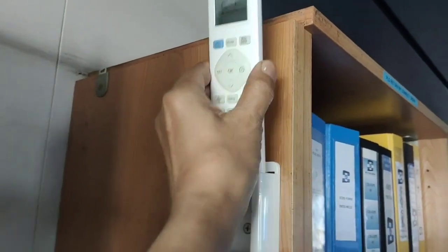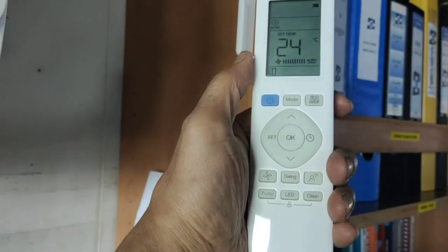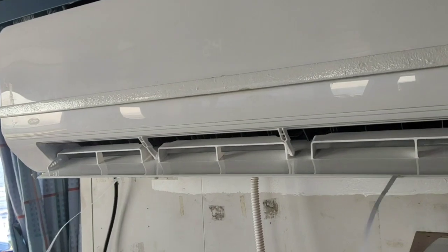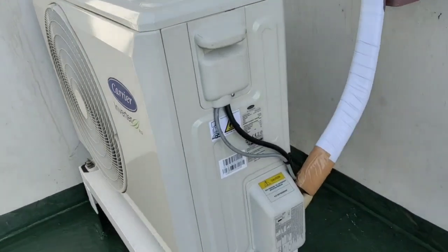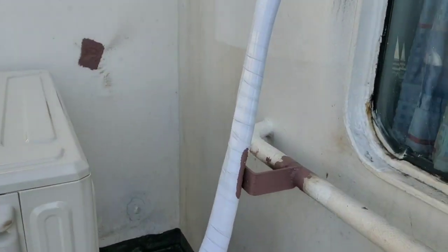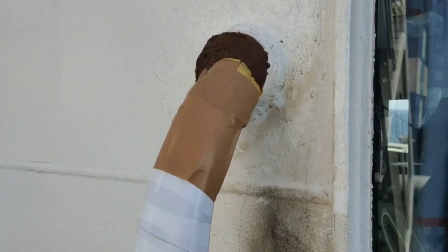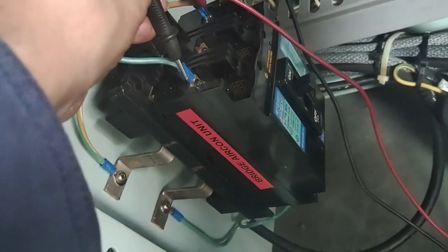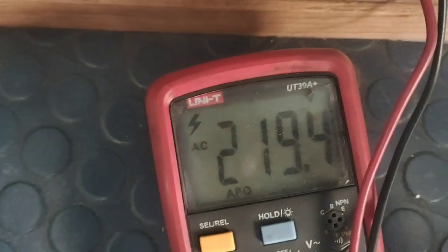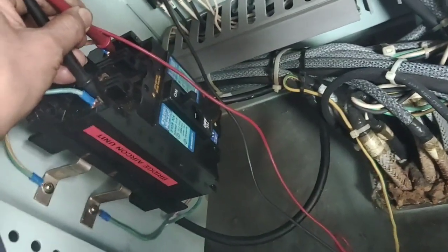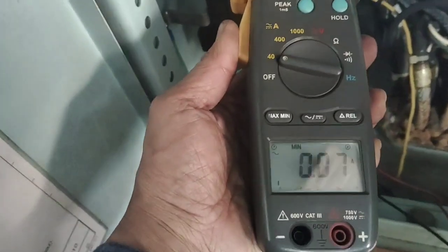The aircon has been running already, started a few minutes ago. It has been set at 24 degrees Celsius, and as you can see, everything looks fine outside, the condenser unit, compressor unit, same with the inside evaporator unit. And now I would like to test the voltage of the unit, if it's okay or the correct voltage or not. And here we can see it is 219.4 volts, almost 220, so it's fine. There's a little voltage difference.